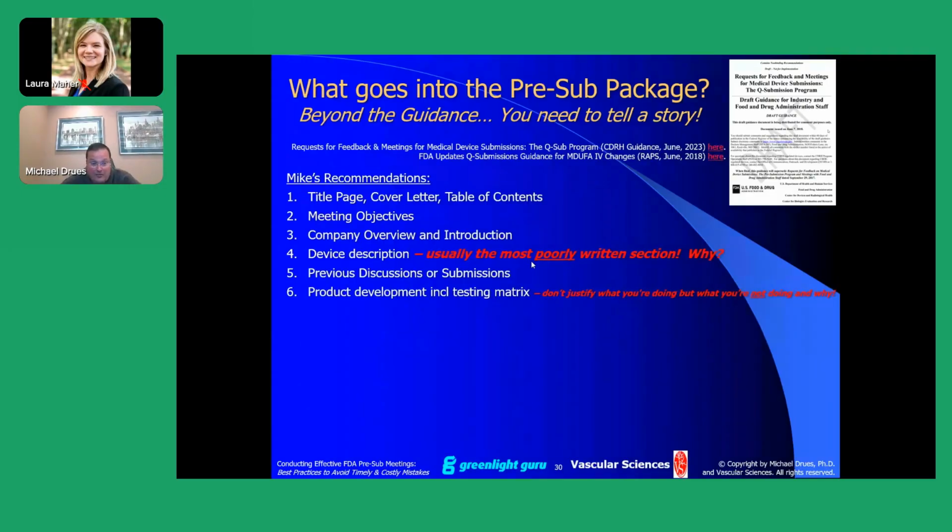Any previous discussions, your product development and your testing strategy. As I've said before, don't just justify what you're doing, but also justify what you're not doing and why you're not doing it. Very, very few people coming into the FDA justify what they're not doing.